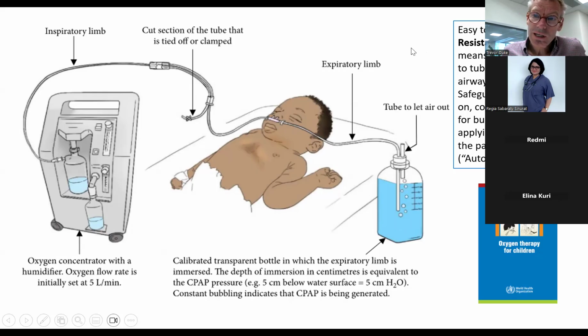It was an efficient and cheap way of providing CPAP, but there are some problems with this. The tubing itself is quite narrow, and sometimes instead of the patient's breathing efforts making CPAP, the bubbling can simply be caused by the fact that the tubing is quite narrow, so that there's high resistance in the tubing. For CPAP to be effective, you need low resistance tubing. That is broader, a wider diameter tubing.